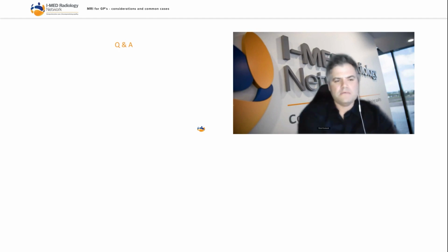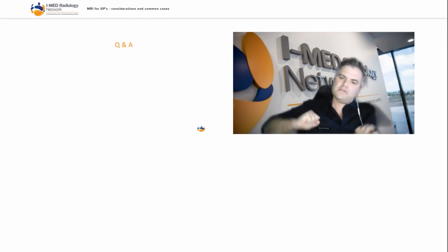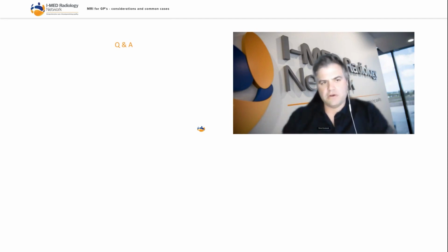Now, the next question we've got was, is there a weight limit for MRI in terms of patients? This has actually become a big issue in America, because obviously they've got a lot of big patients. I think we've got a lot of big patients here as well. Basically, with the standard magnets, there's two issues. The first one is the weight. For most standard MRI magnets, about 150 kilograms would be a standard MRI weight, up to 180. One of the issues, though, is that the bore of the magnet can be quite tight. And if you are very, very large and very, very round, you might not actually fit through the bore. So even though you might be within the weight limit, if you're very short and very wide, you still might not actually fit in the magnet.